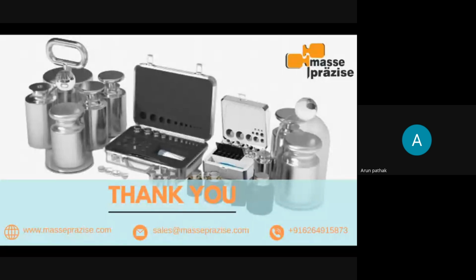In a calibration certificate, the methodology of calibration is given as ABBA cycle. Is this the standard method, or is there any other method? If yes, why is the ABBA cycle preferred? Yes, the ABBA cycle is mentioned in the standard, that is in OIML R111. There are more cycles like ABA, like ABN, based on what type of accuracy you require.